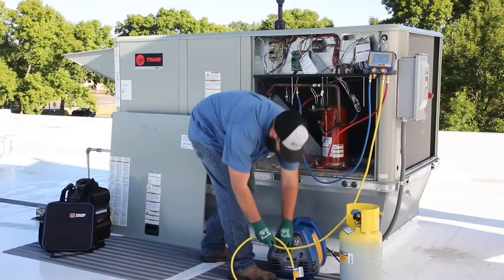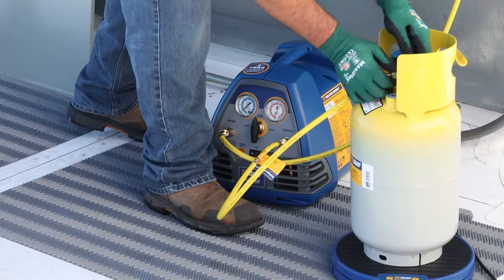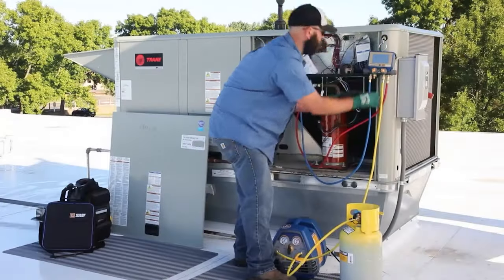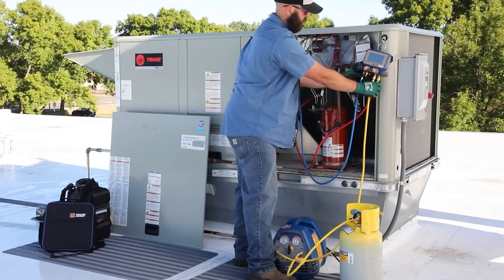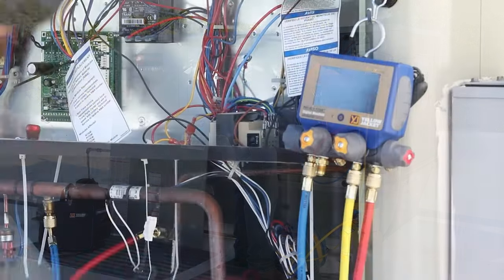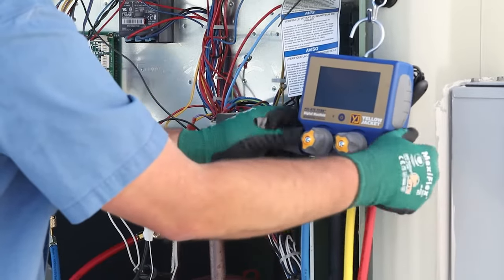Connect the tank hose to the discharge port. It's important to purge the air from the manifold and hoses before starting the recovery. With the tank valve closed, open the manifold valves. The wireless refrigerant scale has an integrated Bluetooth radio that broadcasts its readings to any smart device.